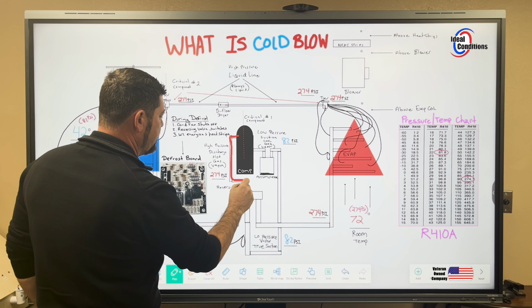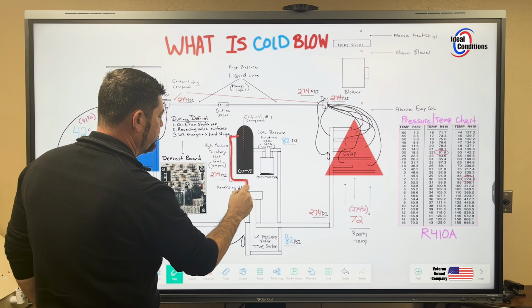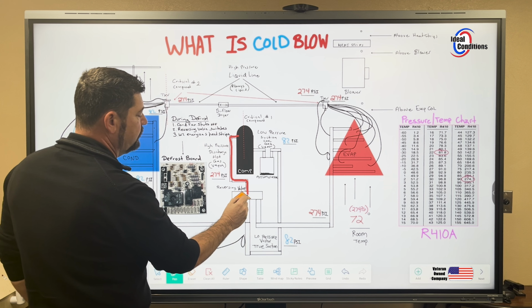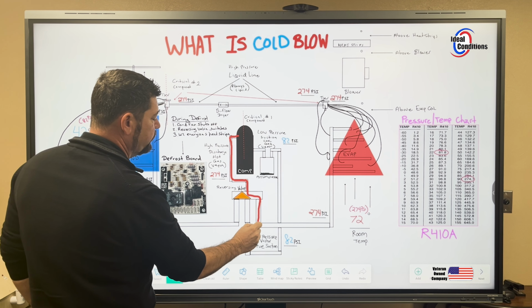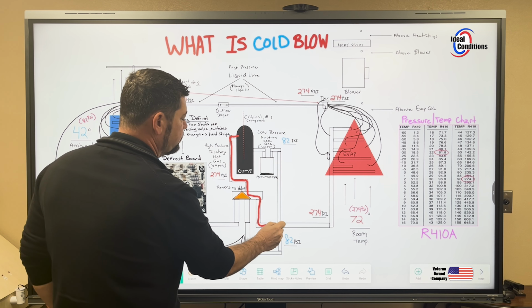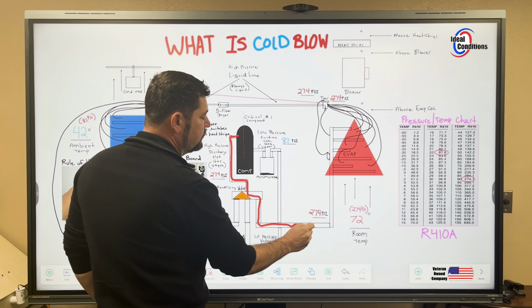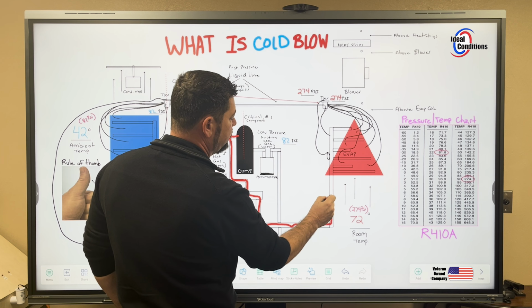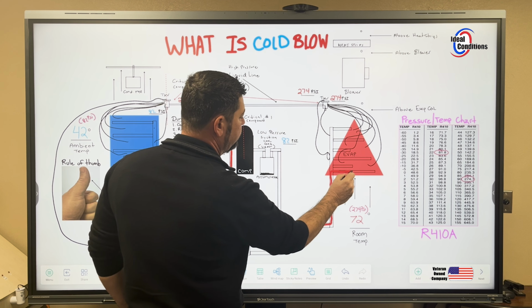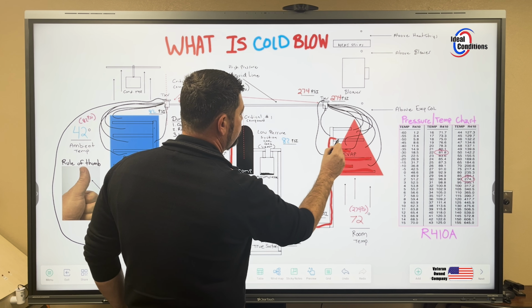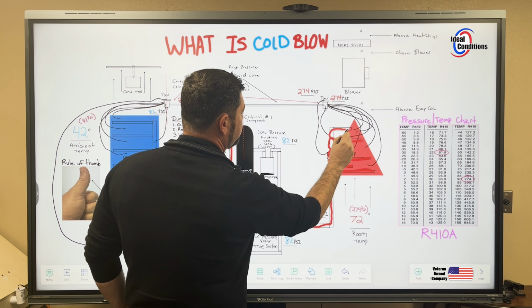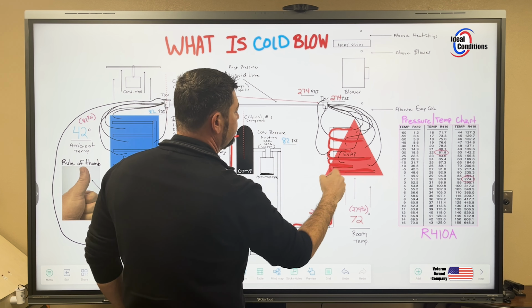As that discharge gas comes across this reversing valve, it can only go in one direction because the valve is shifted over to the far left, blocking it from going to the condenser coil. So this hot gas is entering this evaporator coil, and as that air moves across that coil, we're taking that warm air and dispersing it throughout the entire house.